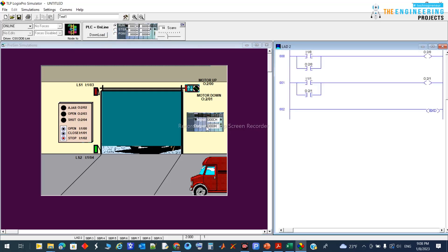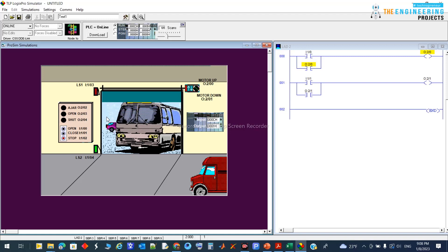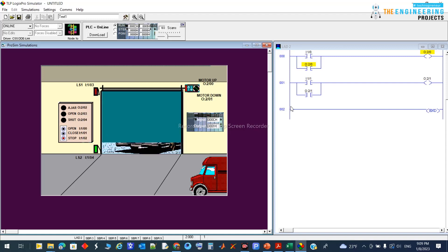Now I want to show you what happens without limit switch logic. I download the program and run it — requesting open, it continues opening with no problem. But let's see what happens when it reaches the end position. You can see: the motor is overloaded and damaged. That is a very bad approach.